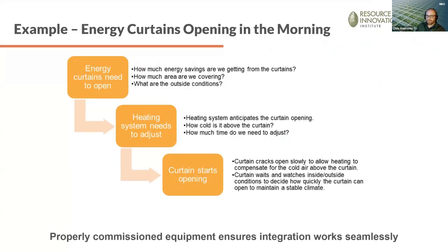So a great example I could think of, as far as integration goes, is energy curtains opening in the morning. Think of a cold winter day. Some cold winter days are colder than others if you're in the north, but it's kind of all the same. If we have our energy curtains closed and we want to open them in the morning, you have a cold layer of air sitting on top of that energy curtain. So first thing we need to know is all of the information that goes into commissioning. We're going to ask ourselves, how much information can we gather on this installation?